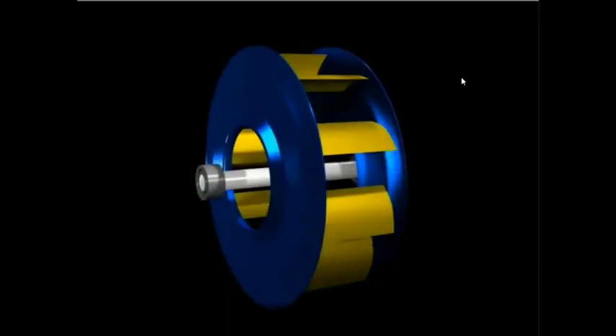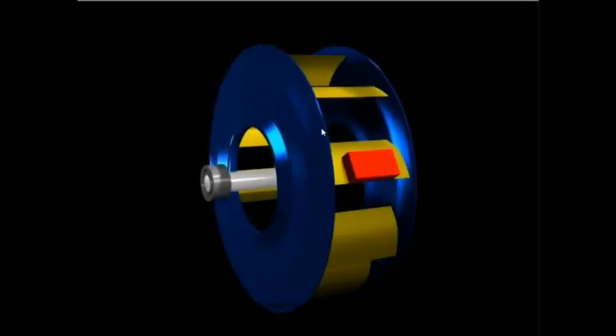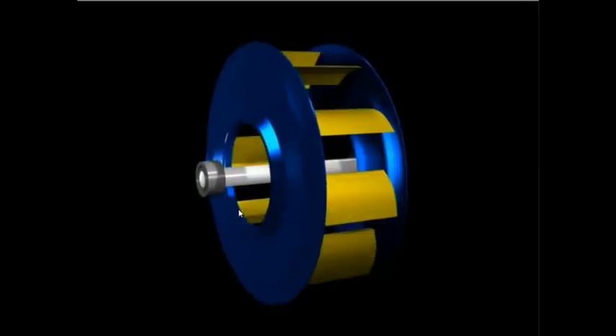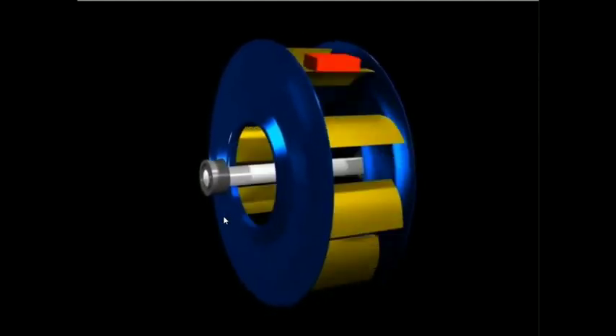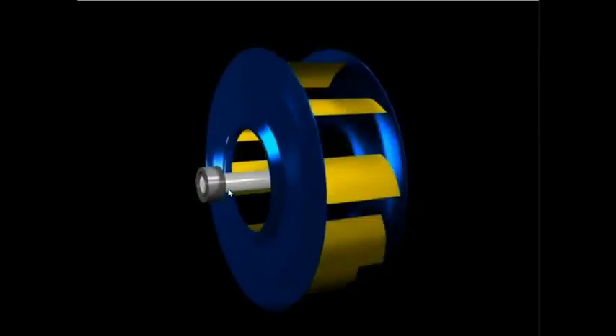So if we have static unbalance, it's all in one plane. Number one, we see that the motion is at the running speed, so we see the high 1x peak. Number two, if you look closely, the motion here is circular.